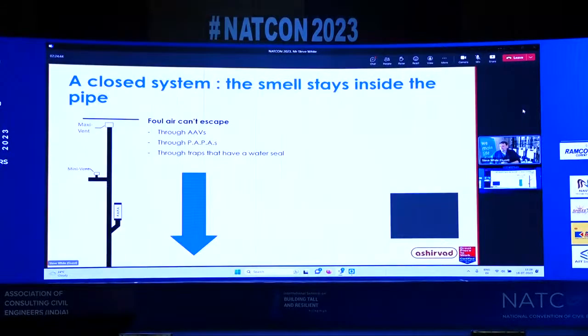So there's a lot of trends, especially post-COVID, of having podiums, rooftop gardens, and swimming pools, and we're using space vertically within our high-rise buildings for more green space. But what we don't want is sewer vents, open vents, near where people are. So we can actually close the system down with the active devices so that we have no roof penetrations, so you can use these green spaces, and any smells go in the direction of flow, so they go downwards out the drainage system.